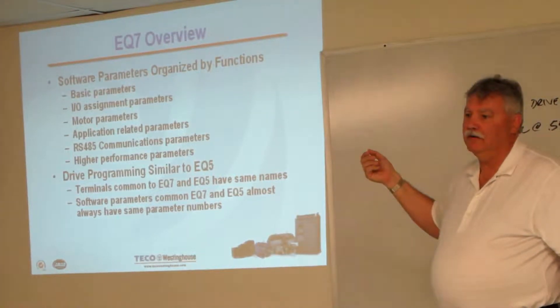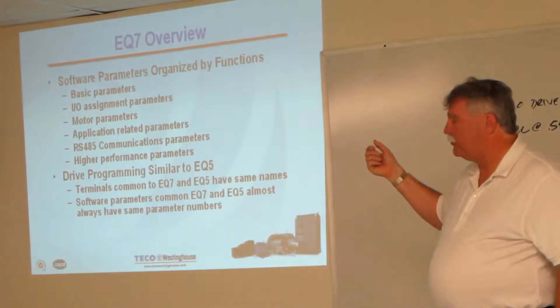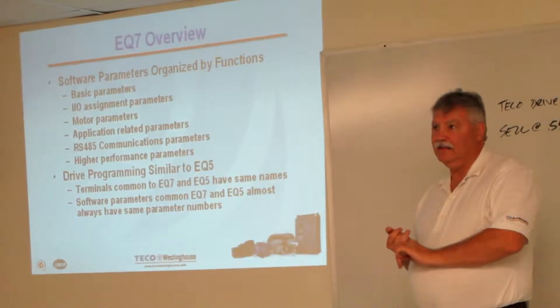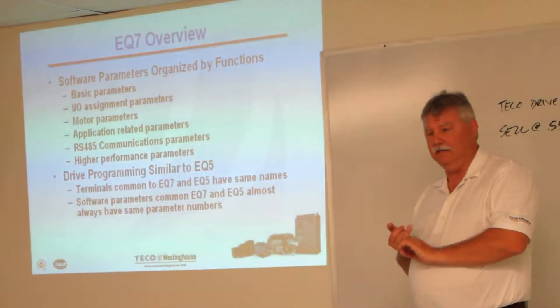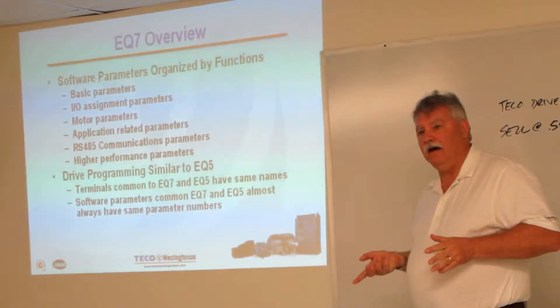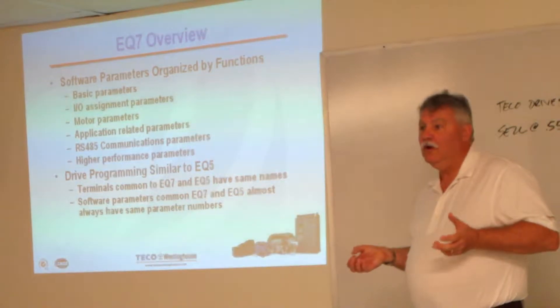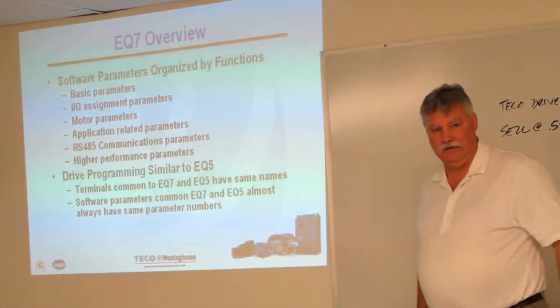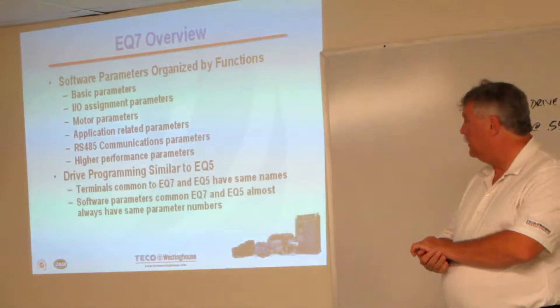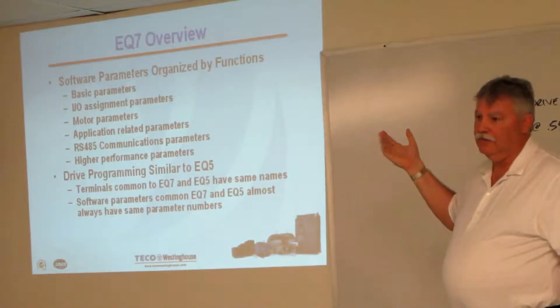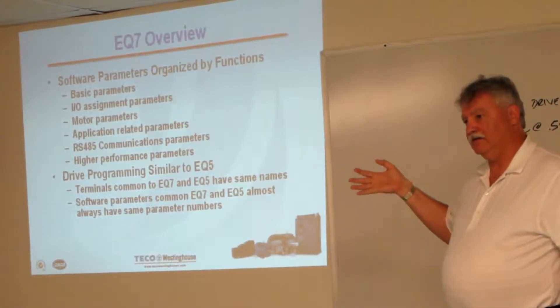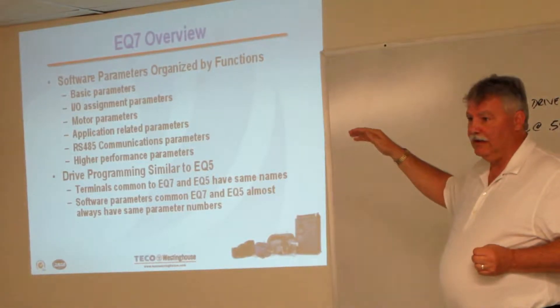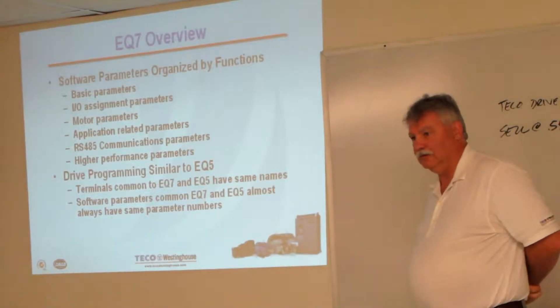Important, of course, is the motor that you're going to couple the drive to. We have a family of parameters that allow you to talk about the motor. Usually the most important thing — and probably the only major thing — is the current. But there are some applications, not in HVAC or fan control, where a few more things about the motor, like the number of poles and the base speed, become important. It's pretty much a given with fans and pumps. The motor full-load amp is a big thing because that sets up the protection in the drive. The drive has internal UL-approved overload protection, so when you put in the motor amps, you're essentially setting your overload detection.